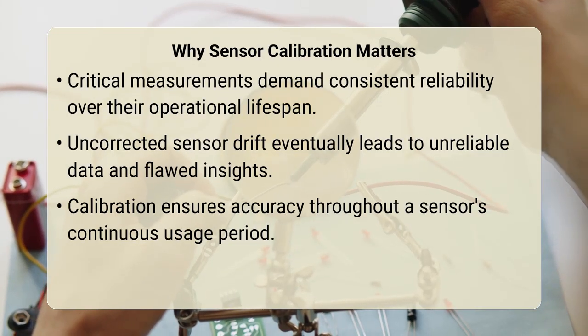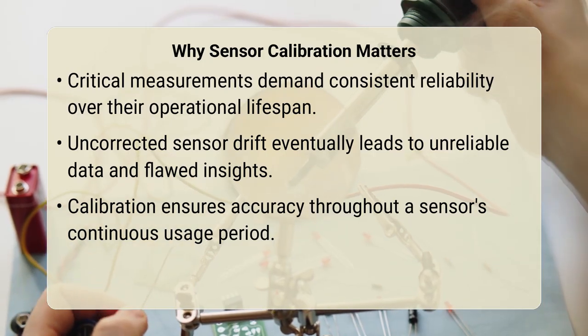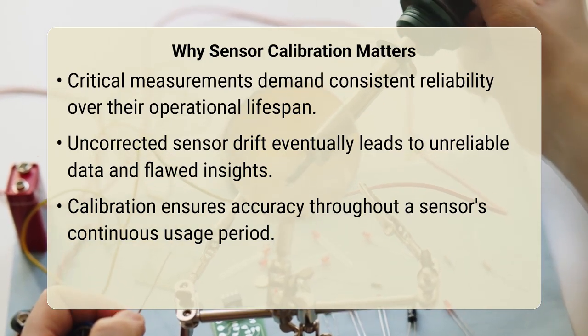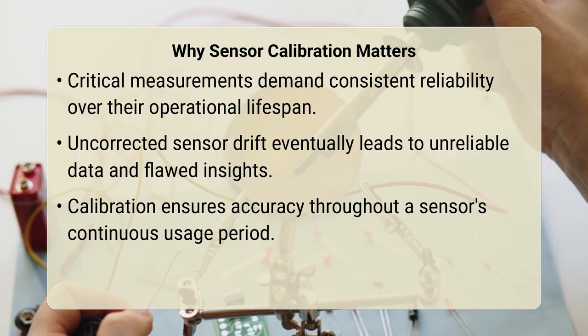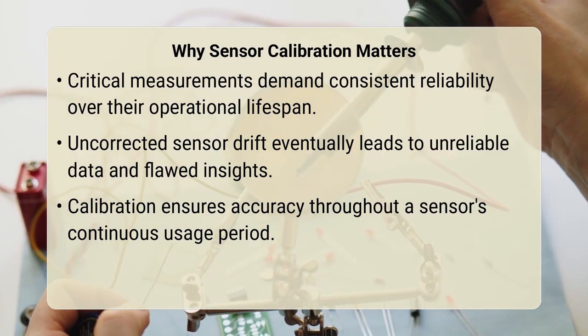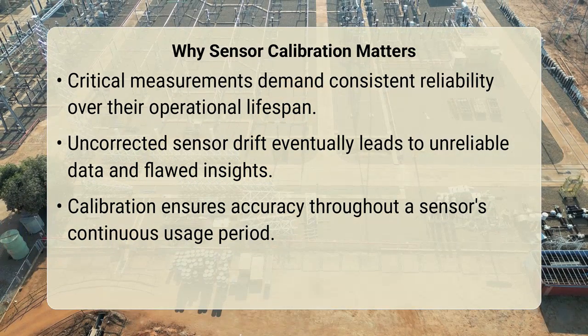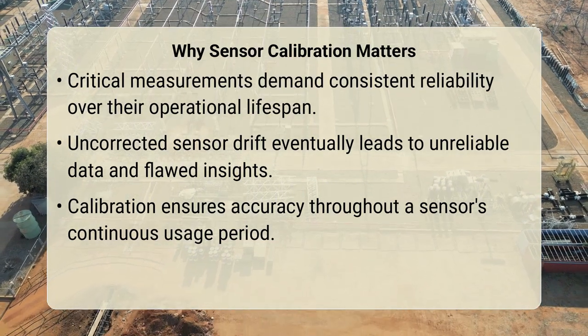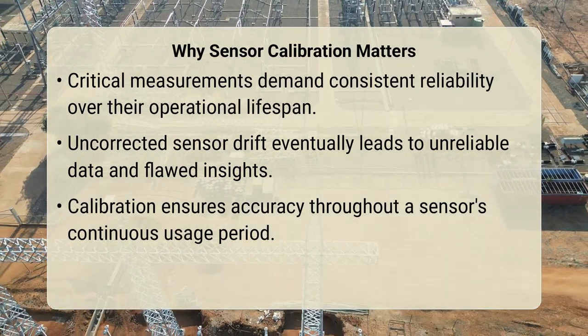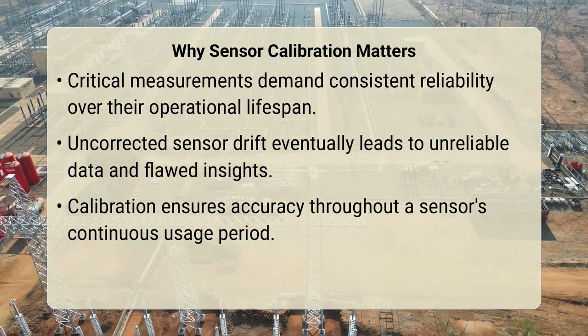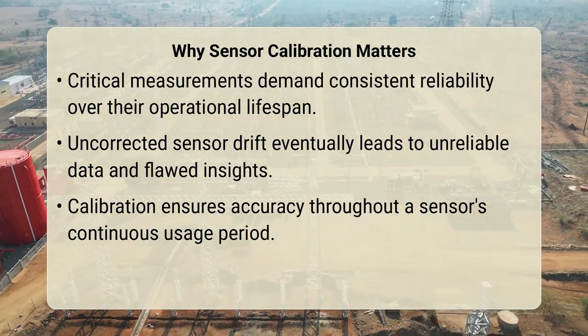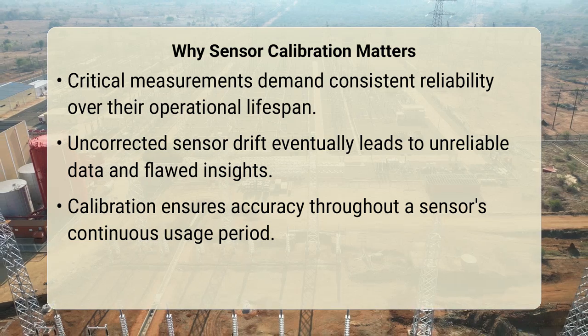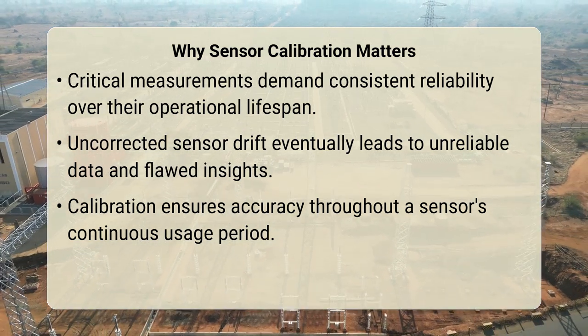Imagine relying on critical measurements, like those from medical devices or industrial control systems. What happens if those readings slowly start to become unreliable over time? Sensor drift correction is an essential part of calibration because it ensures the continued accuracy and reliability of sensor readings over their entire operational lifespan.